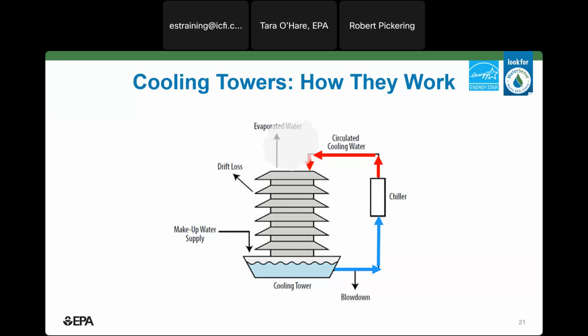This is by design and is the purpose of the cooling tower. Some small quantity of water is often lost via small water droplets that spray from the tower. This is called drift. Some water is discharged as blowdown to keep minerals from building up in the recirculating cooled water loop, the cooling tower water loop or the condenser water loop. And then makeup water is added to balance the losses due to evaporation, drift, and blowdown. We'll talk about each of these in a little more detail now.